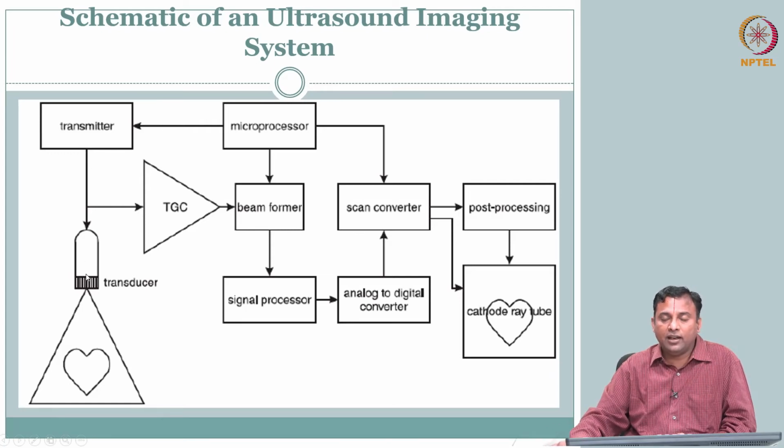The transducer, as we will see, is an important aspect, because it is generating the sound waves and also receiving the ultrasound waves. After that, it's all about converting it into some sequencing. Again, we will talk about the beamformer to some extent. What we will not talk about is all the scan conversion, ADC, post processing, display; all this we will go a little light on.